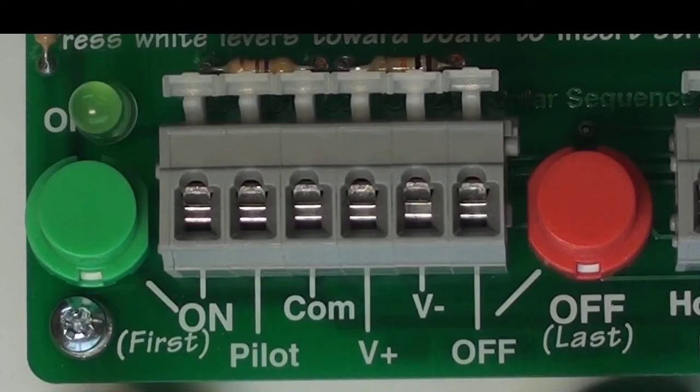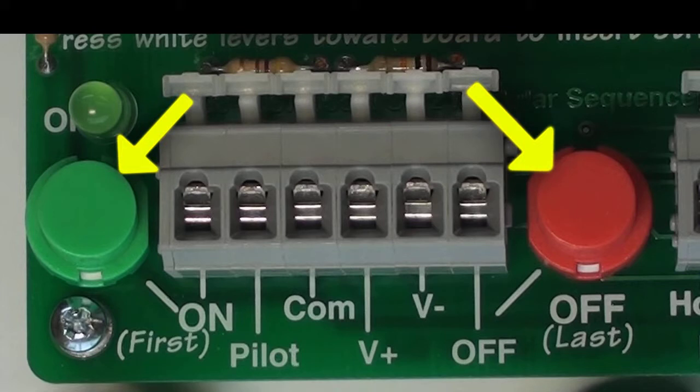Before we get started connecting switch wiring, Lyntec recommends that you verify the operation of the system using the built-in test switches. These green and red test switches are located at the bottom of each sequencer circuit board. Start the on sequence by pressing the green button on the first circuit board. To sequence the system off, press the red or off button on the last sequencer board.